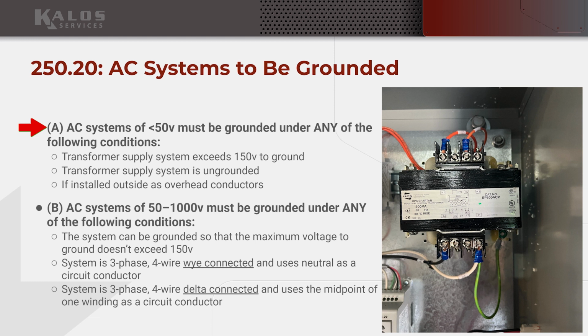And so maybe we're not going to see a secondary grounded that frequently, actually, in AC systems of less than 50 volts ground. Oh, so this is inclusive of 24 volts. Interesting. So there's probably a lot of bonding out there of our secondaries to ground that is not happening.